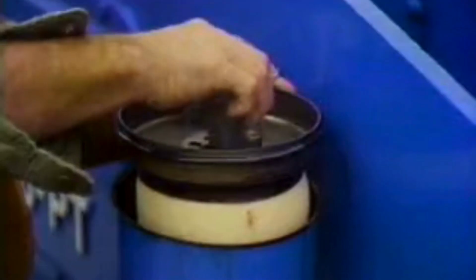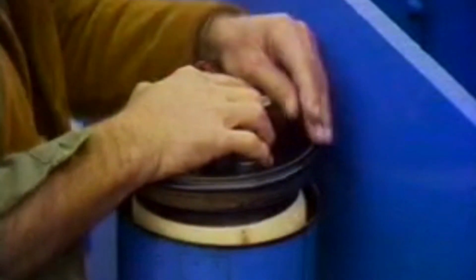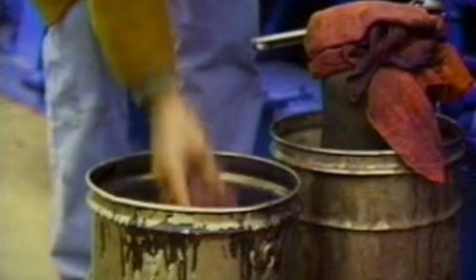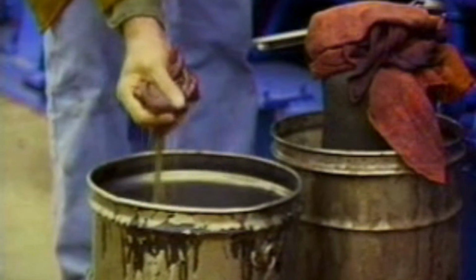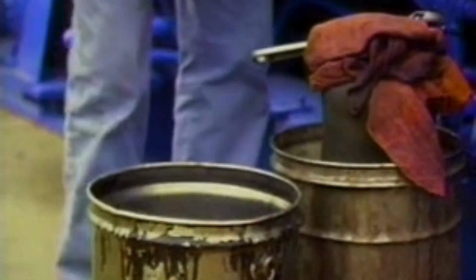Clean the magnetic filter once more and install a new element in the cartridge-type filter. Don't forget to clean the filter case. If you're simply changing the oil and not flushing your pump, you should still clean up any sludge in the crankcase and check bolts for tightness. Cleaning and changing filters is also important.